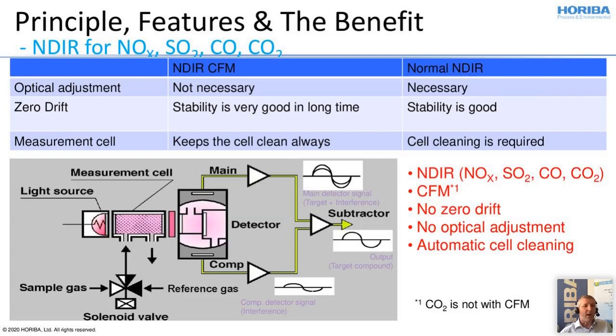So where are the differences between HORIBA and the standard principles? We have the so-called cross-flow modulation with NDIR monitoring, which we use for NOx, SO2, CO, and CO2. We do not need optical adjustment. When you look at standard NDIR monitoring, it is possible that you need to adjust the optics once a year. With this cross-flow method, there is also very stable performance over a long time. So what are we talking about?